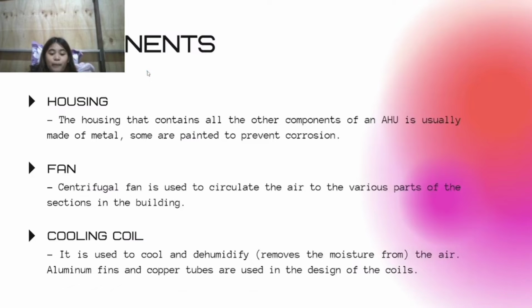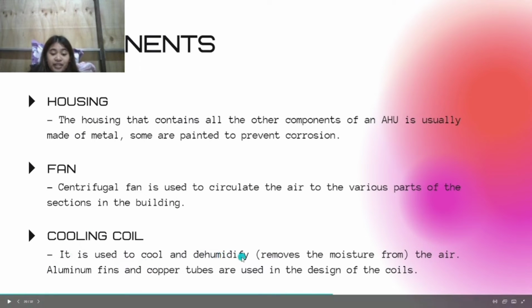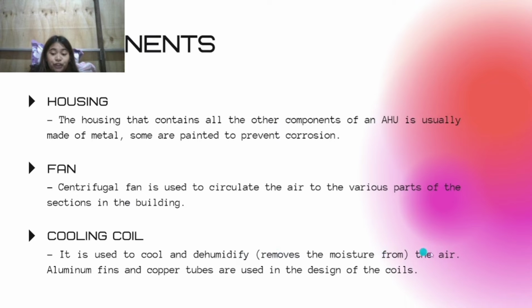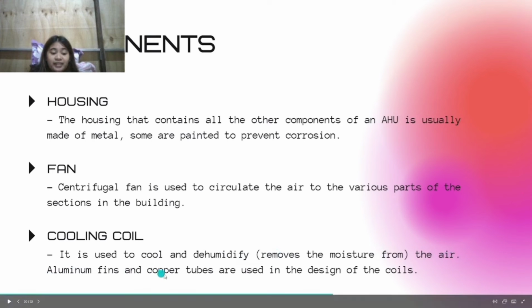There are 6 components for an air handling unit. First, housing. The housing contains all the other components of an AHU and is usually made of metal, but some are painted to prevent corrosion. Second, fan. A centrifugal fan is used to circulate the air to the various sections in the building. Next, cooling coil. A cooling coil is used to cool and dehumidify, which means to remove the moisture from the air. Aluminum fins and copper tubes are used in the design of the coils.